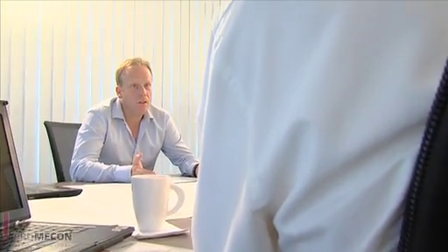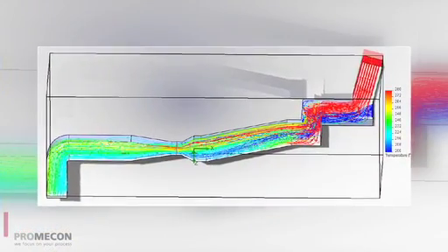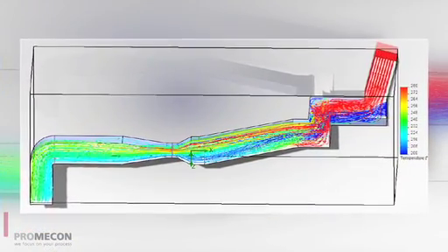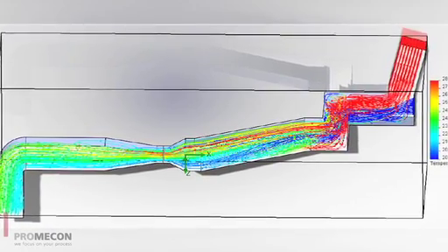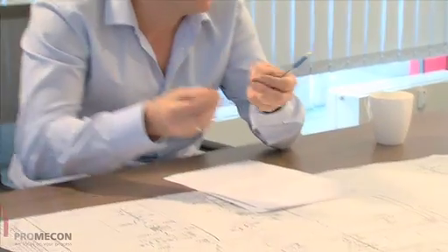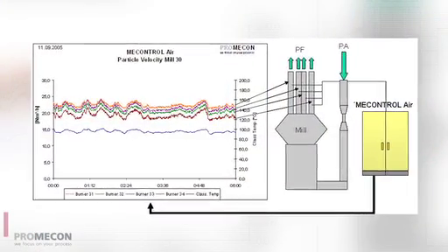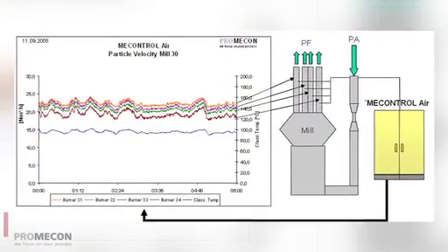That's definitely an issue of airflow through the mill. The airflow is at least as crucial as the coal mass flow. We certainly have a problem determining how much air goes into the mill, but the other question is: do we know how much air is necessary through the mill? With our new technology, you can measure airflow out of the mill, so you know what the velocities are as the mill is operating. By that, of course, you can have a much better handle on heat consumption and the drying process, and that itself also has a big impact on the grinding and the fineness of what comes out of the mill.